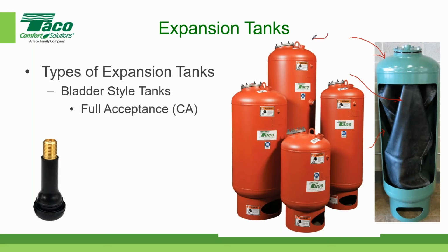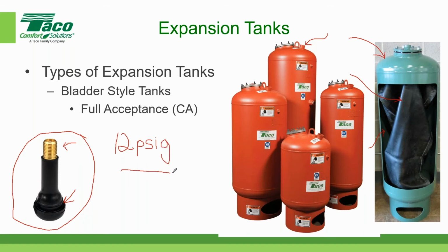Now, at the top of the tank, there's a little collar that protects the Schrader valve. And I have a picture of the Schrader valve over here on the left-hand side. It's exactly the same valve that you find in your car tires. It may not actually have this mounting mechanism down here, but the valve itself is basically the same that you find in your car tires. And that's where we can add compressed air. And when we add compressed air, we add it to the void space, and that's on the outside of the bladder and inside of the steel container. Now, when we ship expansion tanks from the factory, we pre-charge that air side, that's again the void space, to 12 pounds per square inch gauge. 12 pounds per square inch. So we ship it from the factory pre-charged to 12 psig. All right. So now let's look at, oh, and one other thing.